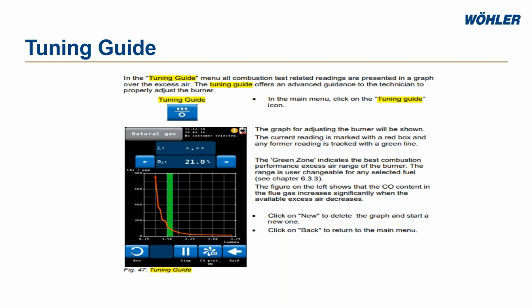On the left-hand side of the graph you have your CO levels, and on the bottom you have your excess air. The red box or circle is the current reading, and as you can see, we're way far from the sweet spot, so we have some adjusting to do. This green bar changes depending on your fuel type - the analyzer determines the sweet spot by what fuel type you have. This is a factory setting or recommendation of what the excess air should be, or what your sweet spot should be.